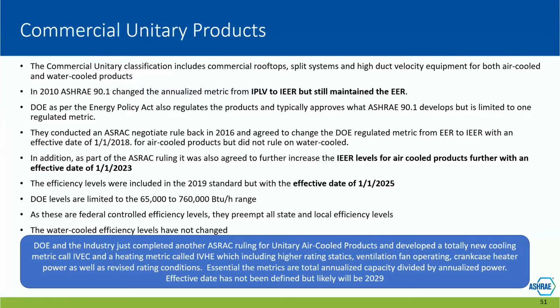One thing I'll note too, at the bottom, we just completed another ASRAC ruling. Not like we don't have enough to do, but the new ruling is a radical change. In 2029 you're going to see all new metrics for commercial rooftops - a thing called IVEC, integrated ventilating energy cooling efficiency, and an IVHE, which is very much like an HSPF, an annualized metric for heating. Those are radical changes. The metrics will now include economizers, ventilation, and crankcase heater power. So a lot of changes, and significant improvements in efficiency again in 2029, anywhere from 16 to 36%. Next slide, please.